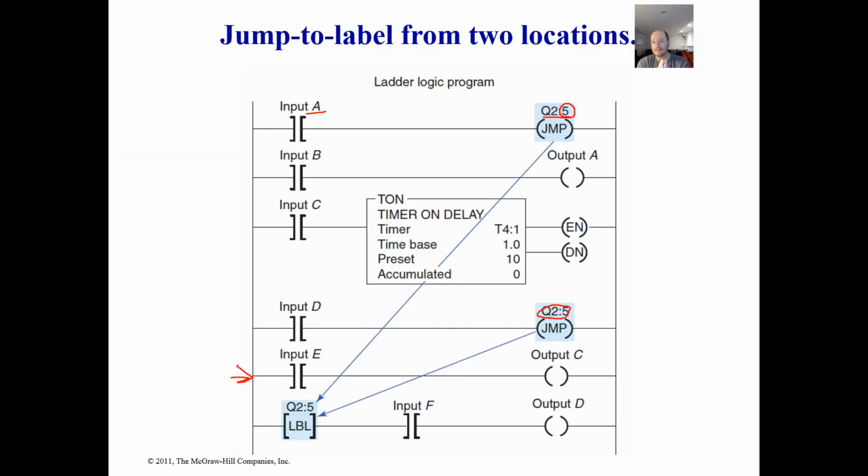So the one last thing I want to talk about with the jump to subroutines is you have to be very aware of where you're jumping into. If you have multiple jumps and your label here, for example, is trying to jump into a zone that is turned off, it can cause some major scan time issues, and they can actually fault your program out, okay, which we do not want. We do not want your program faulting out. That is bad. So you have to be aware of that. Just be cautious. Again, try them, but be cautious with them. Okay.